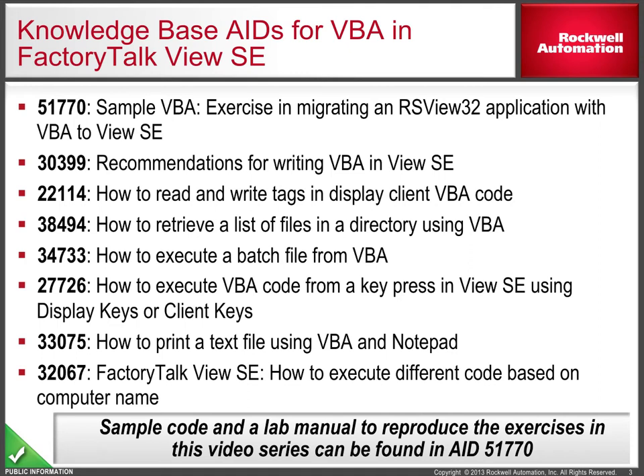This simple example was meant to give you an idea of how you can begin to migrate RSView 32 VBA code to View SE. As you've seen, some modules from View 32 can be reused in View SE with modifications. You can also import code temporarily in order to copy and paste from it. One final note. Keep in mind that there is functionality native to View SE that may replace some of what your RSView 32 VBA code was doing. For example, language switching or numeric entry limit checking.